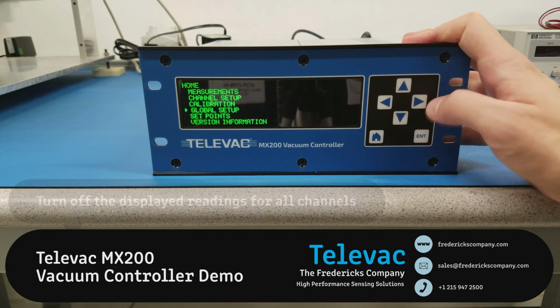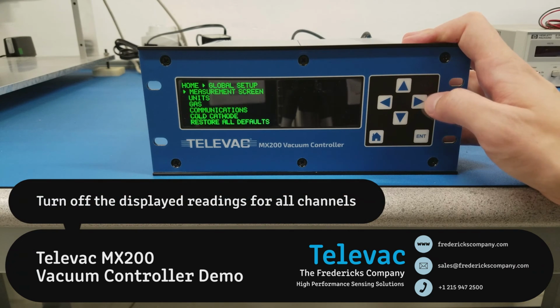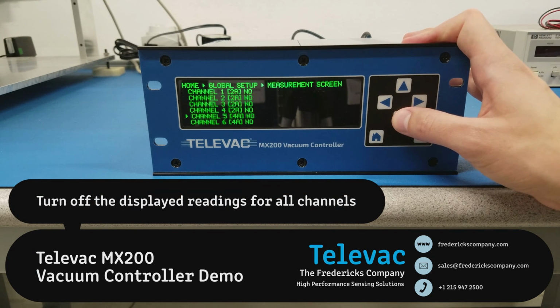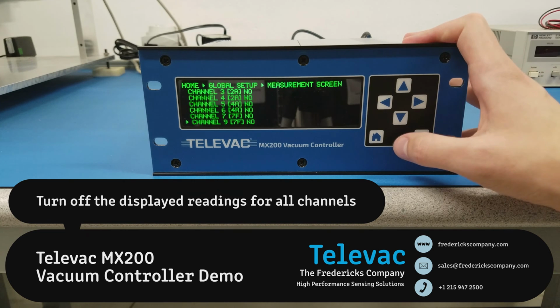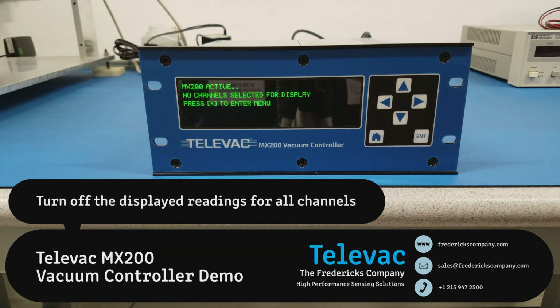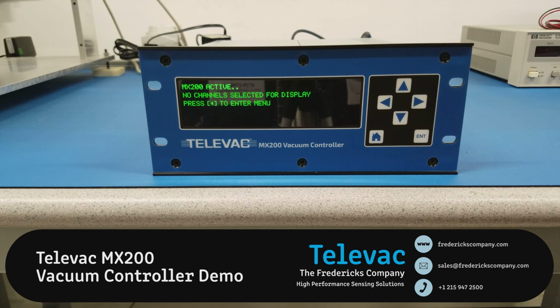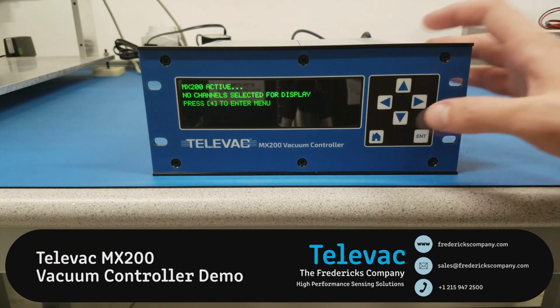And then finally, there's an additional feature on the MX200 which allows you to turn off all of the measurements on the measurement screen, and then you'll see this display. And this is effective for situations where you have the MX200 hooked up to a PLC and you don't want the user comparing the front panel readings to the readings on their PLC.